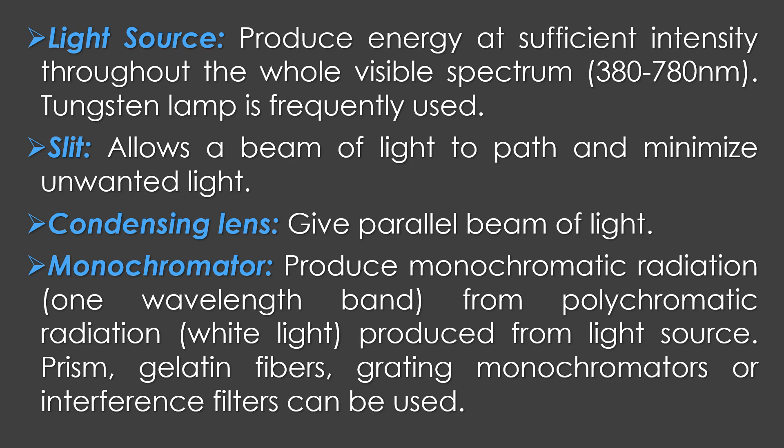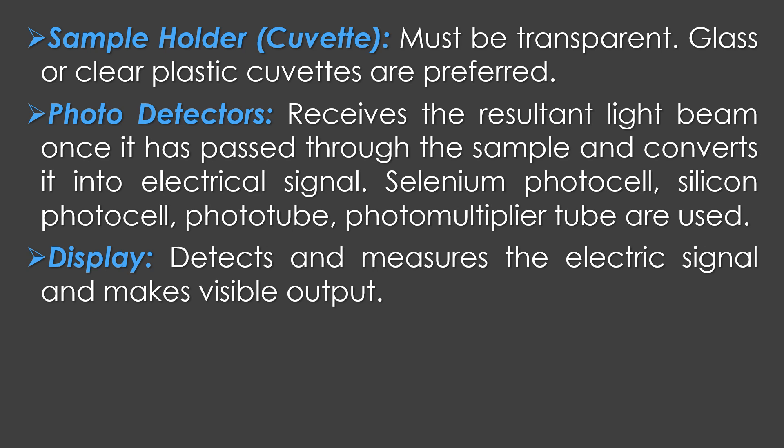The sample holder or cuvette must be transparent; glass or clear plastic cuvettes are preferred. Photo detectors of the colorimeter receive the resultant light beam once it has passed through the sample and convert it into an electrical signal; selenium photocell, silicon photocell, phototube, photomultiplier tube, etc. are used as photo detectors. Finally, the display detects and measures the electrical signal and produces visible output.